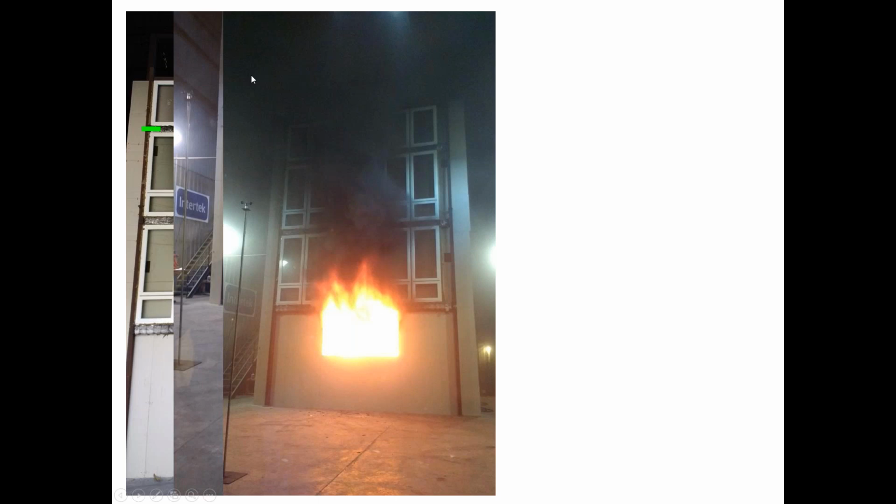And there's so much fuel used in this test that the fire actually comes out of the chamber, recruits new oxygen, continues to burn, and makes a big flame front coming up in front of the windows, which are essentially one story up from there. And like I said earlier, anything that's directly behind that flame front basically gets turned to ash. But that's okay. It's not necessarily going to compromise either of the two criteria to pass the test.